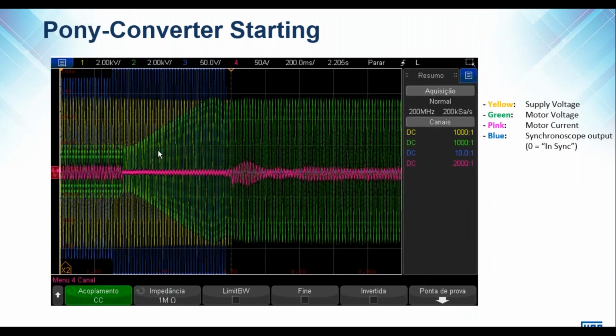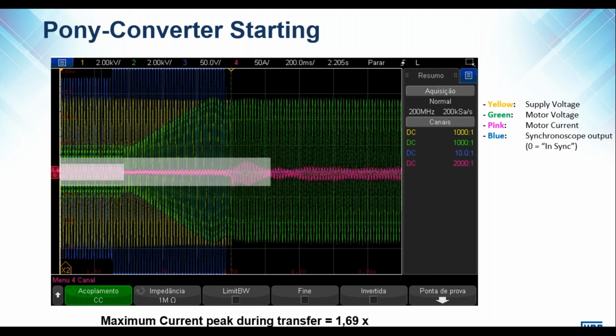Just to show that same bypass in terms of what it does to the current. This is the motor current during the VSD startup and run phase. The current then dramatically reduces when we open the VSD output and increase the voltage from the excitation. And then at the point of synchronism, there is a small increase in current when we bring in the bypass contactor, but it is not more than the full load current of the machine.